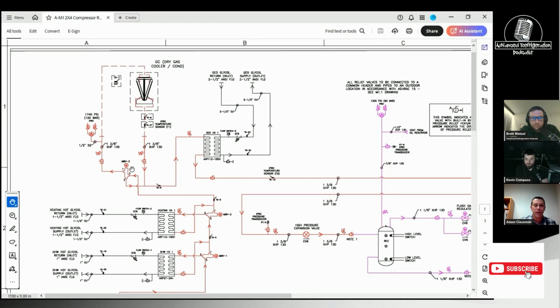If this valve opens up too fast and starts dumping hot gas, that just causes a chain reaction. Up the line, the high pressure expansion valve will see an increase in input temperature, and then the subcooling, because it's running subcritical and controlling your subcooling, will adjust, and then you get a lot of erratic behavior. That temperature will increase, the valve will close, and then you start to see the cycling of the high pressure expansion valve, the fans, there's all sorts of bad things that happen. When this valve starts to open, it should take minutes, if not 10 minutes, to go from 0 to 10 or 15% until you start seeing a noticeable effect.